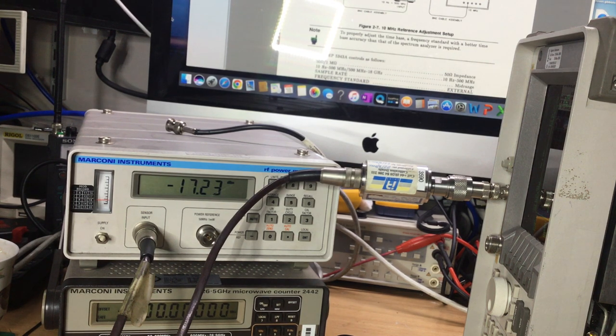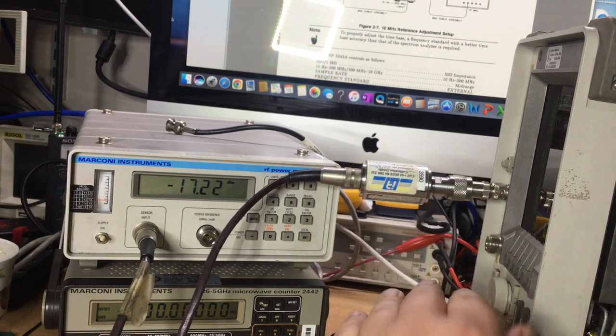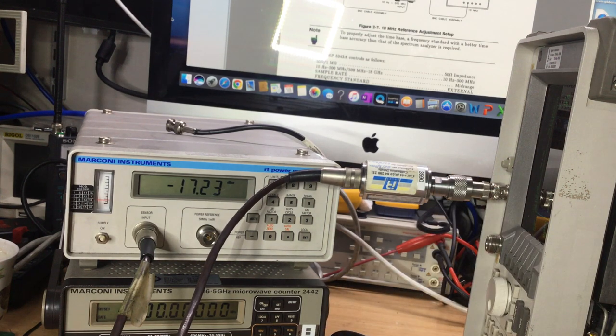Okay, well, obviously if I feed an RF signal in on the type N connector there from the signal generator, if this has been calibrated to a reference that was off to start with, then potentially it will read incorrect anyway. If it's gone through that cal sequence and the level's been too low and it's obviously not read the right level and frequency, it may have wandered off. And so there may not be a problem with the input, it might just be down to the calibrator.